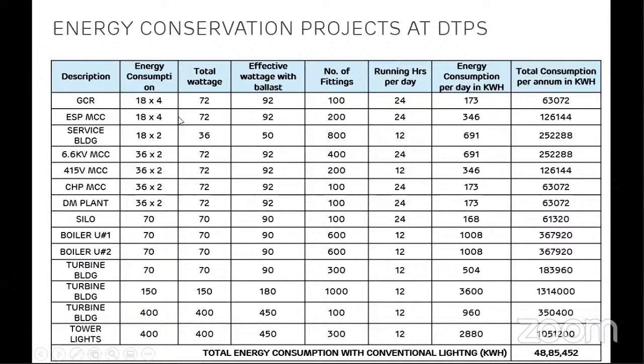So in our plant, we installed these LED lights considering all these benefits and energy saving initiatives. These are different buildings in the plant: GCR, ESP, service building. Now the energy consumption was 18 watts per fluorescent lamp and 4 such lamps, so total wattage was 72. There are ballasts installed in tube lights, so the effective consumption was 92. Total number of fittings was 100, running for 24 hours a day.